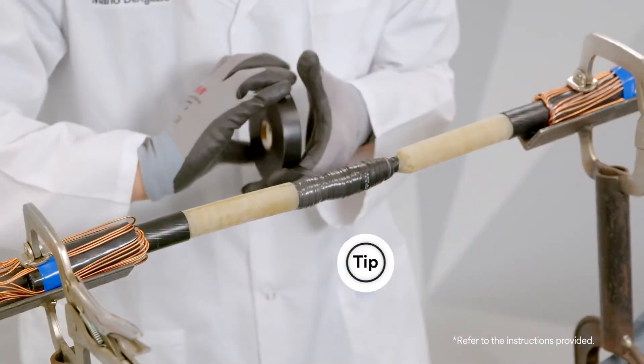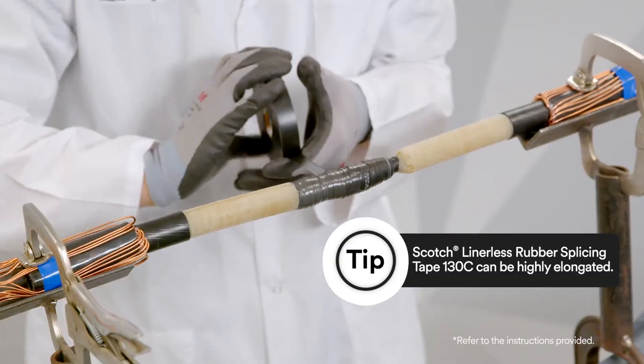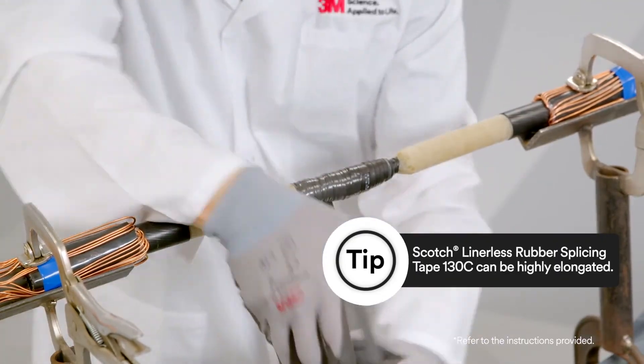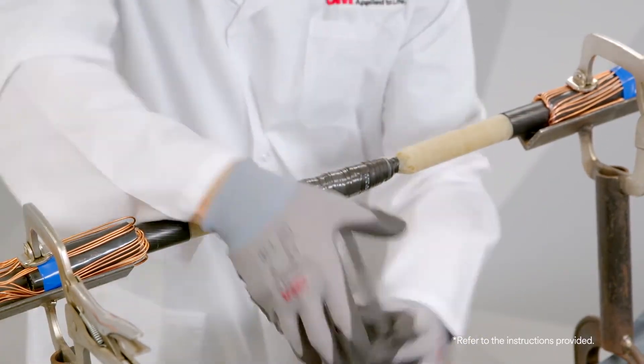Make sure you apply enough Scotch Linerless Rubber Splicing Tape 130C to build up the thickness to one to one and a half times the original insulation thickness.